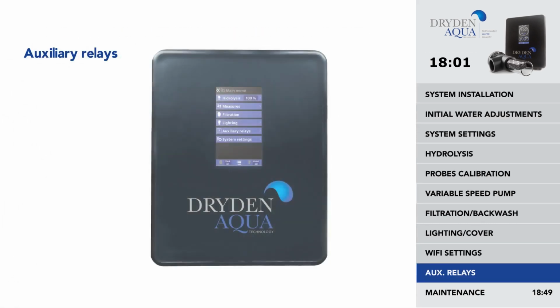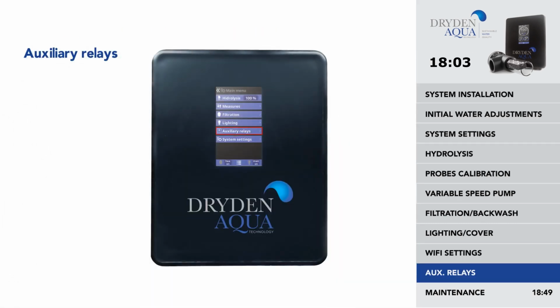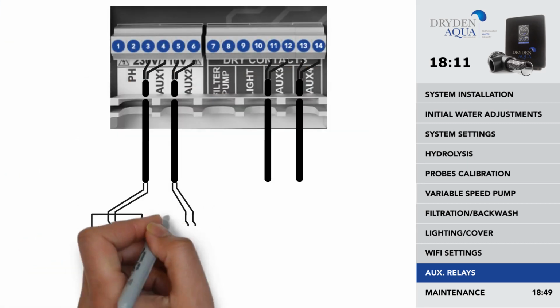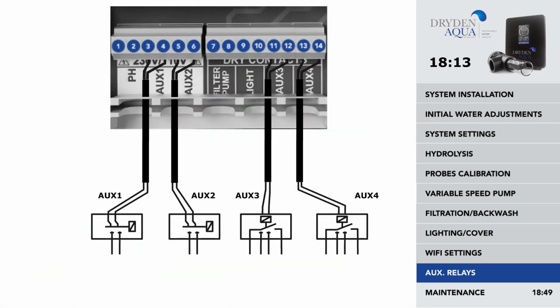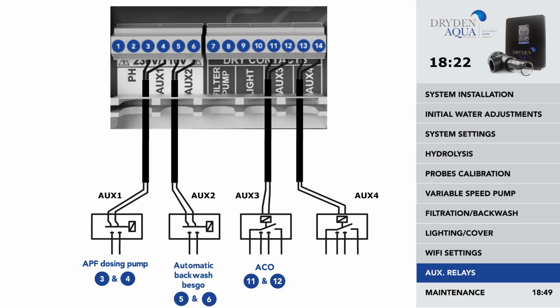Auxiliary relays. It is possible to control up to 4 extra auxiliary relays, such as water attractions, dosing pumps, and more. As a default setting, you will only see 2 available relays, APF and ACO, under Auxiliary 1 and 3. Auxiliary 2 is reserved for the BESGO automatic backwash valve, and Auxiliary 4 for the heating system. If you don't have a heating system, you can deactivate it to benefit from an additional free relay.